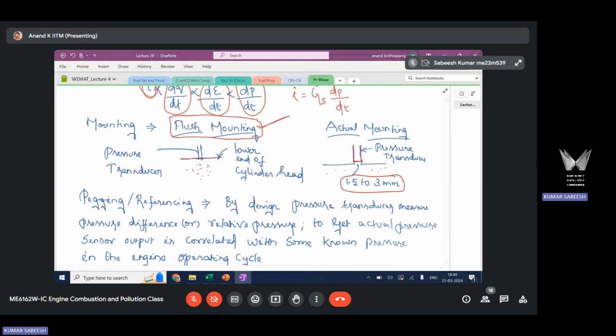But what will happen when you take the sensor in? What is the limitation of taking in the pressure sensor? Or in other words, if you don't do flush mounting, what limitations or shortcomings can you expect? The pressure will not be as exact as present in the combustion chamber. Here it is directly exposed in the flush mounting.